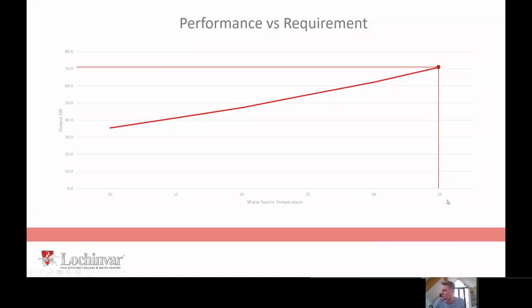So when you're looking at a source temperature of 35 degrees from a water source heat pump instead of 10, which would probably be like the source of a lake or a river or whatever, you're looking at electrical efficiencies of, I mean, I've got the value here. So flowing at 70 degrees centigrade, this heat pump will give you an efficiency of 540% if your source temperature is 35, which is massive.